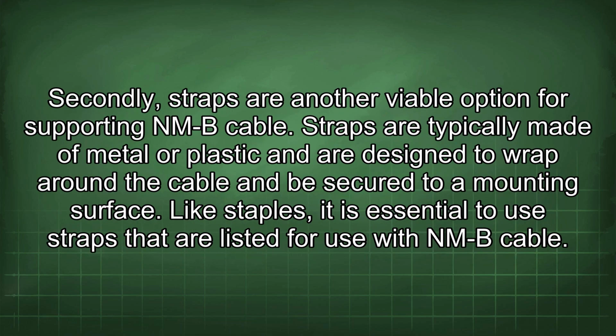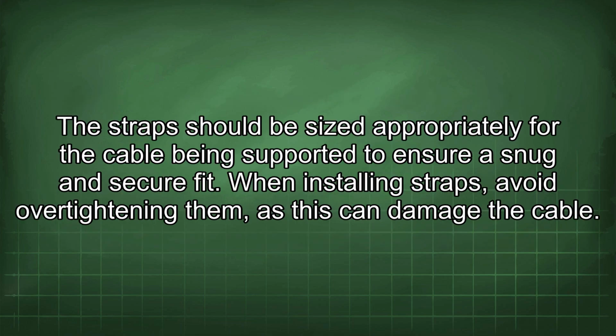Secondly, straps are another viable option for supporting NMB cable. Straps are typically made of metal or plastic and are designed to wrap around a cable and be secured to a mounting surface. Like staples, it is essential to use straps that are listed for use with NMB cable. The straps should be sized appropriately for the cable being supported to ensure a snug and secure fit. When installing straps, avoid over-tightening them, as this can damage the cable.